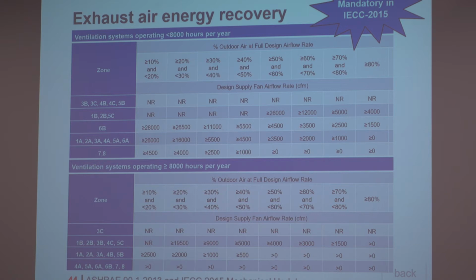And the way that requirements work is you basically have to do total energy recovery. You can't just do sensible energy recovery unless you're in potentially like Tucson or some really dry climate. Potentially you only have to do sensible. But in most of the areas of the country, you're having to do total energy recovery because we're looking at the enthalpy change between the two airstreams. And there's some nuance there, but as you get into colder climates and higher percentage of outdoor air, you're more likely to be triggered to go into energy recovery ventilation. So that's the way that this table's working.